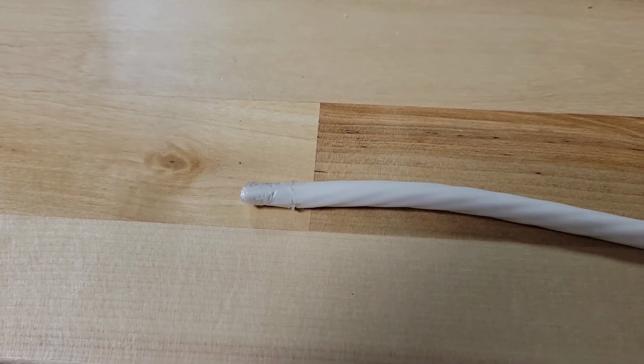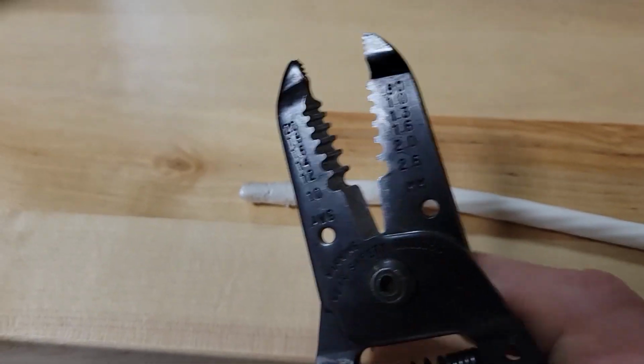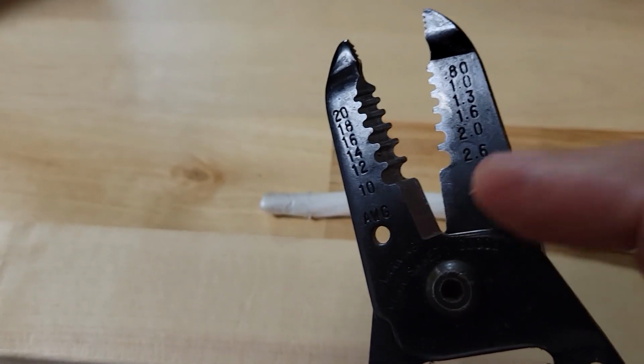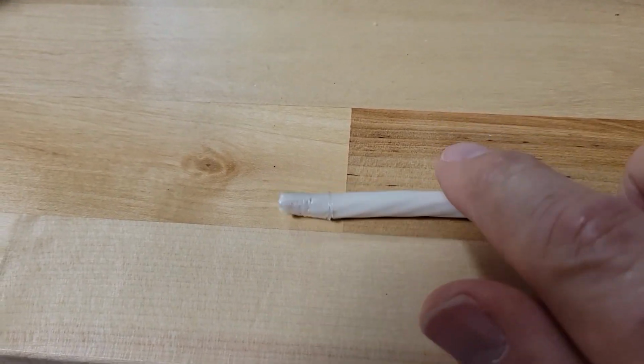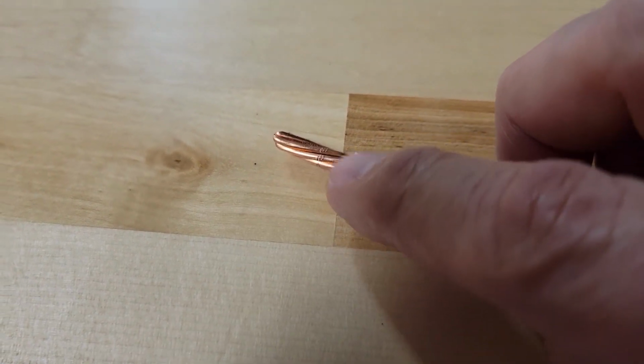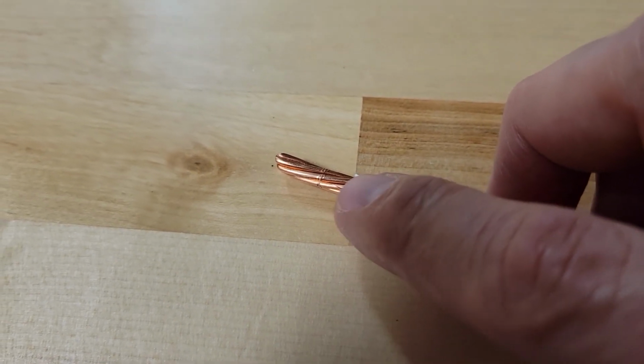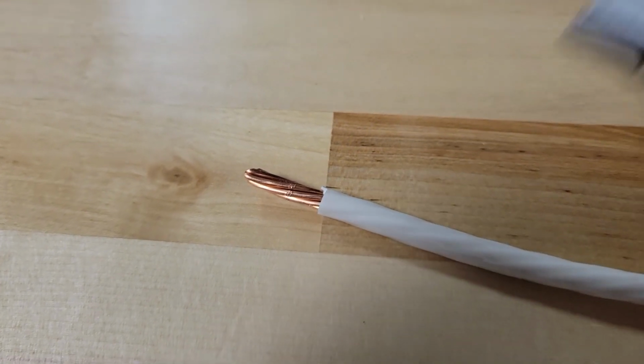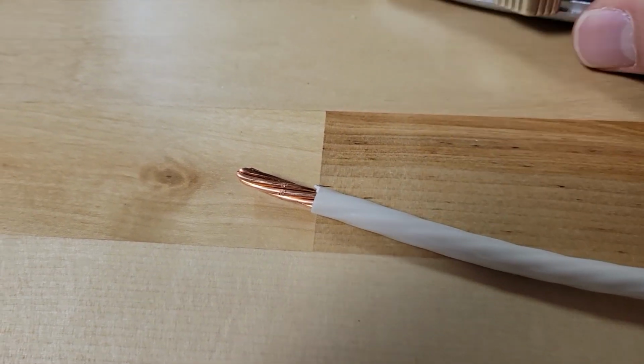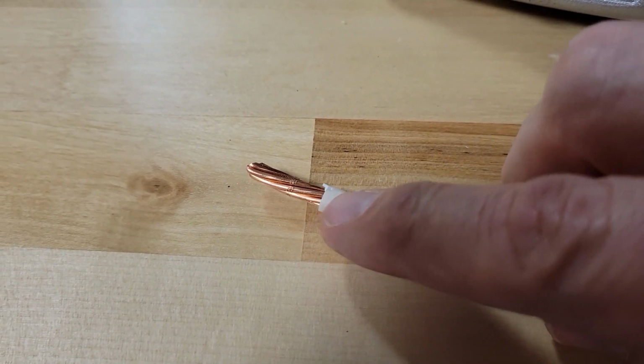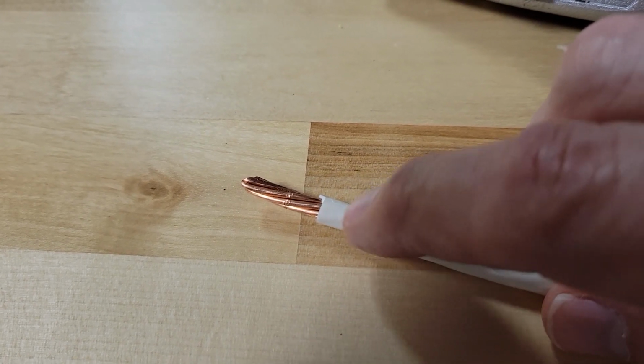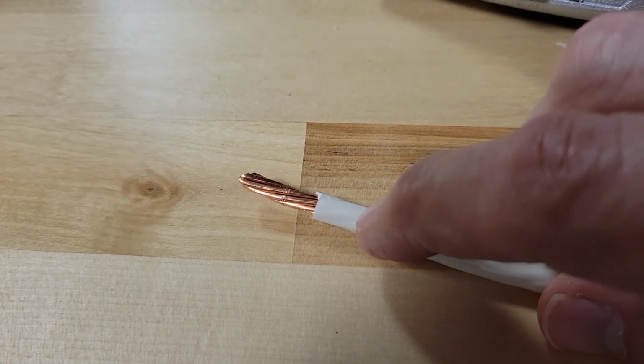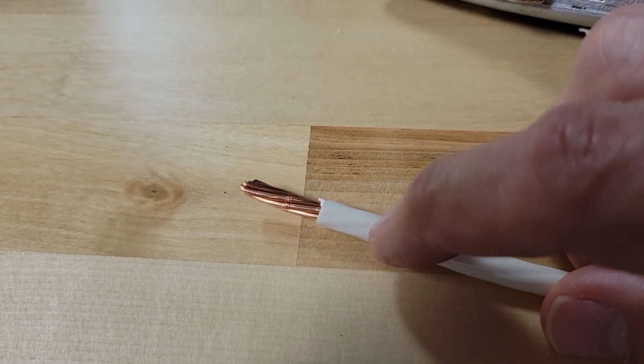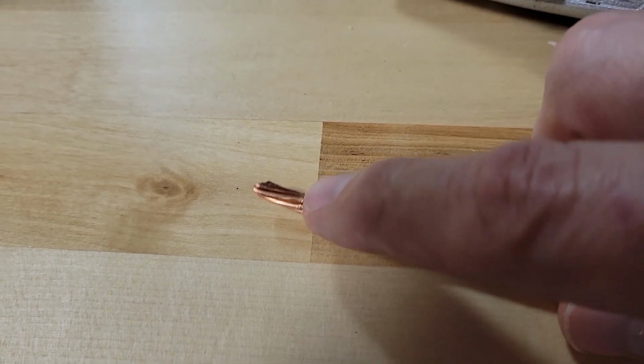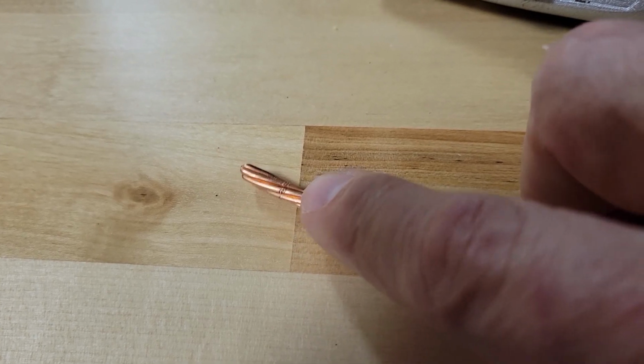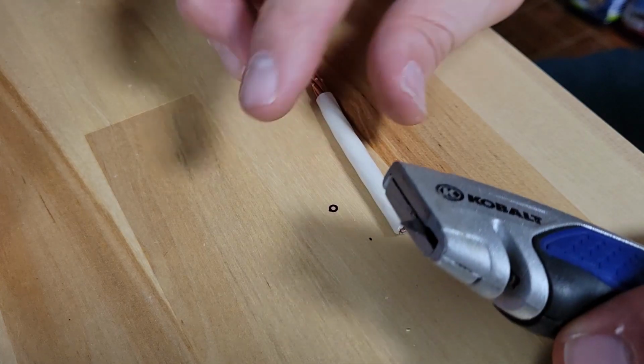When you go to trim off the insulation, you may be tempted to use a tool like this that has a nice sharp edge down here that you can use to trim the insulation. The danger is that you'll nick the strands of copper, and you don't want that. So I find that you're better off using a utility knife. You make your cut going this way, just enough so that you can pull back the sheath, and then you cut around it to the desired length. And that'll eliminate the chances of damaging the strands. So here's a look at how I do it.